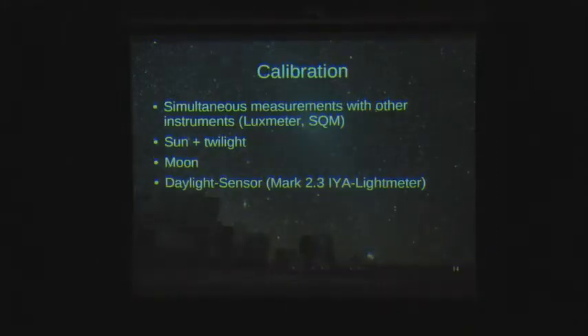And now, how to calibrate the sensor? Once you get the counts out of the instrument, you have to calibrate it to get the lux values or whatever you like to calibrate to. So the simplest way is to do a simultaneous measurement with a calibrated instrument, a master light meter or whatever. What I use now, and is fast and works really good, is using the sun and twilight, because sun and twilight you have every day. For the moon you have to wait sometimes.